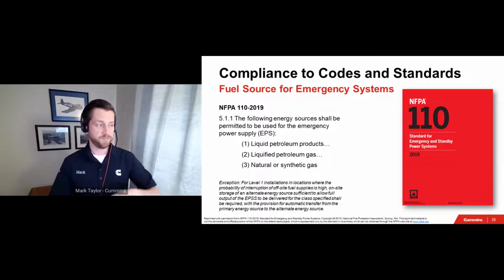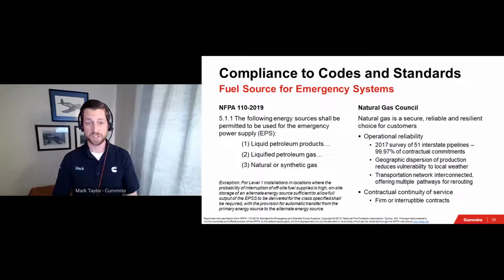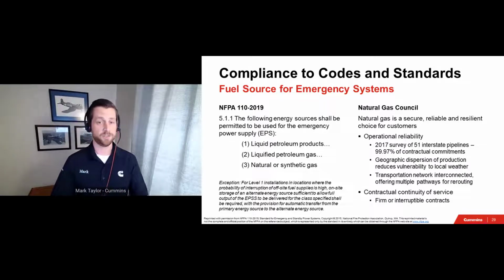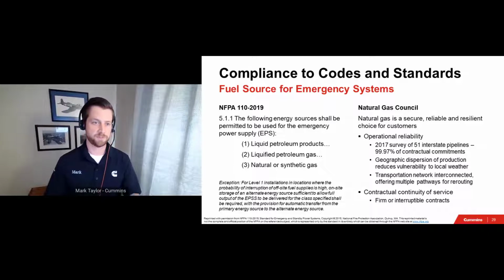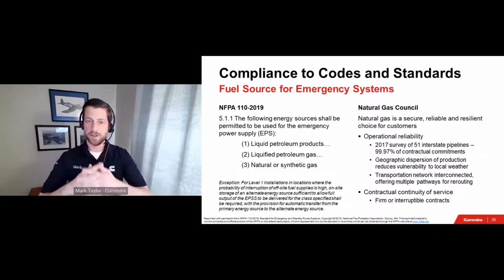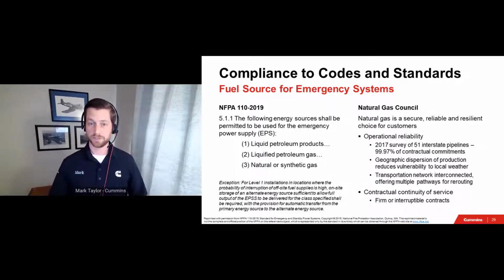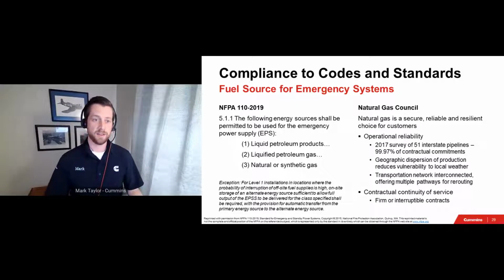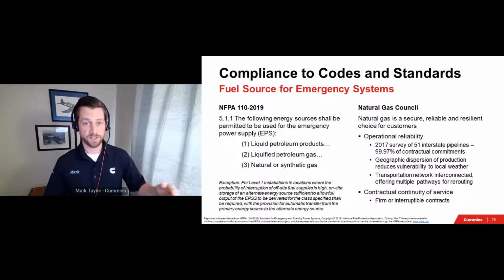In some regions of the country, let's pick on California, for example, on-site storage is effectively a blanket requirement due to it being a seismically active part of the country. For many parts of the country, this discussion can be up to the local authority having jurisdiction and the local utility. To put this conversation that may occur between you, the AHJ and the local utility into context, the Natural Gas Council put out a study that worked to quantify how reliable the nation's natural gas utility really is. Due to natural gas infrastructure having such geographically dispersed production sources and the interconnected nature of the network, the U.S. natural gas network's reliability was quantified to be exceptionally high, robust enough to be considered a primary source of fuel for Level 1 applications.